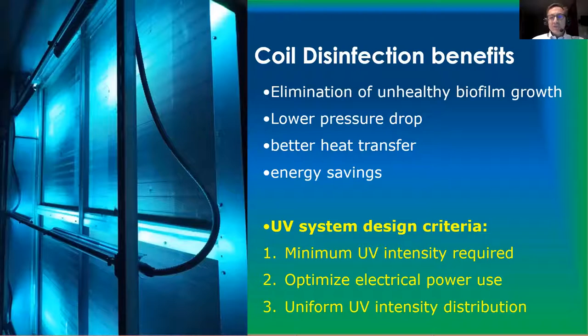What we're trying to do with coil disinfection is eliminate what we call a biofilm, which is pretty unhealthy, as I'll show you. We have seen some pressure drop increases due to biofilm building up on the fins of a coil. And of course, you can see heat transfer being inhibited by the presence of molds on the coil. You end up having energy savings if you can get rid of them. The design criterion is to deliver UV intensity as uniformly as possible on the surface to be disinfected.